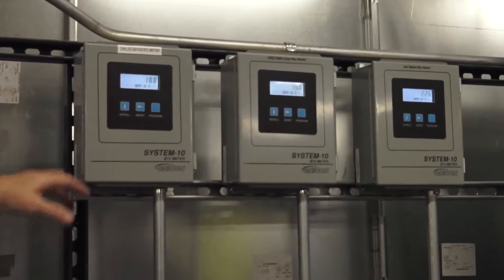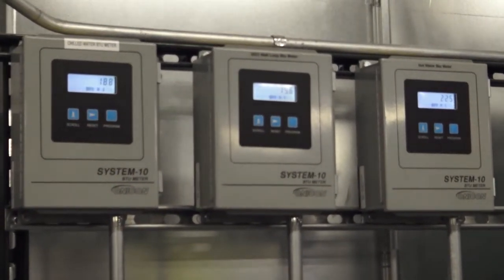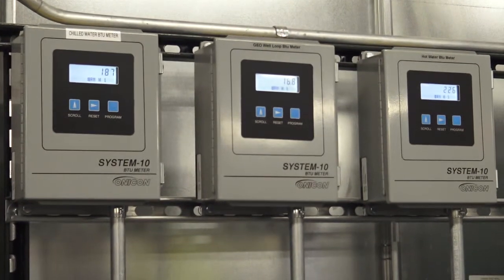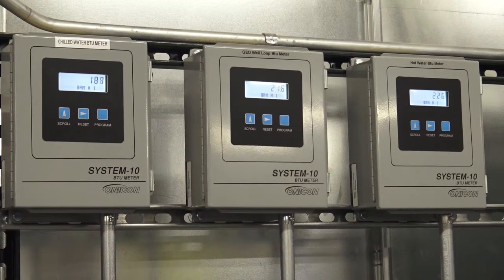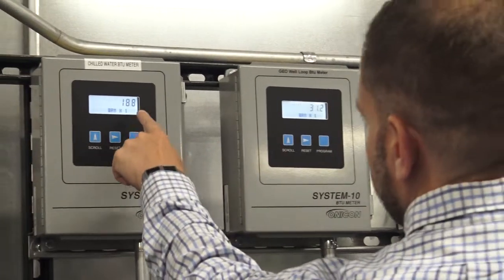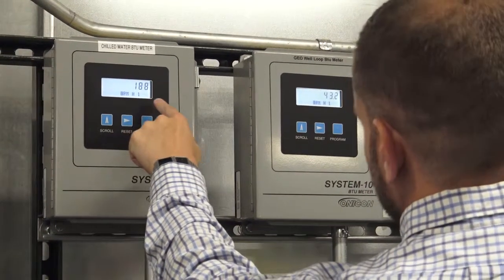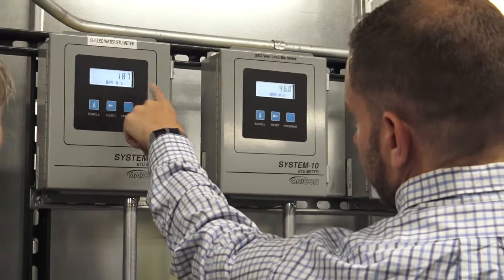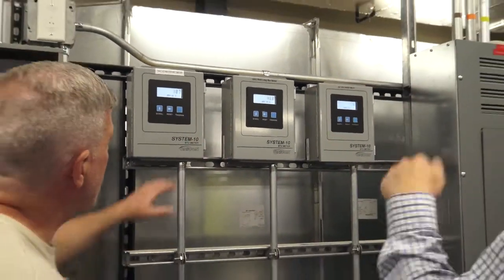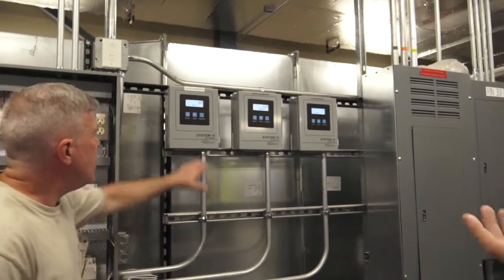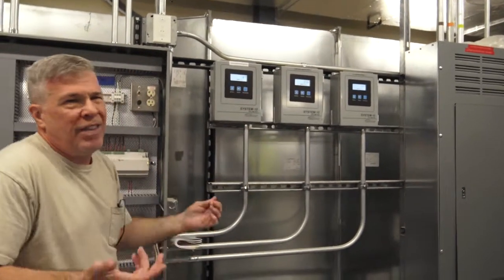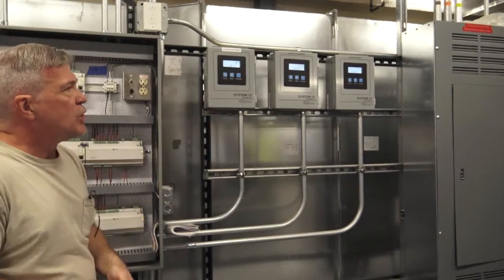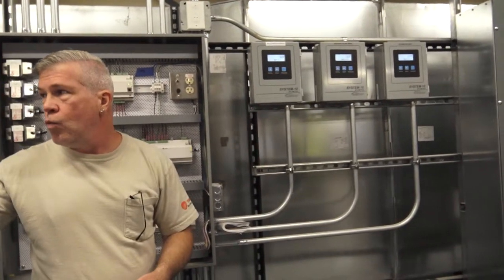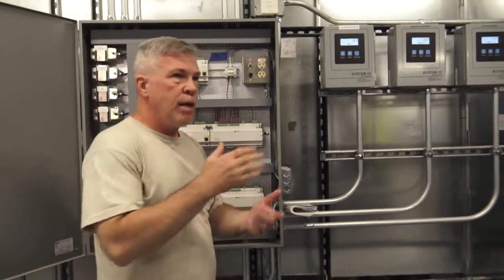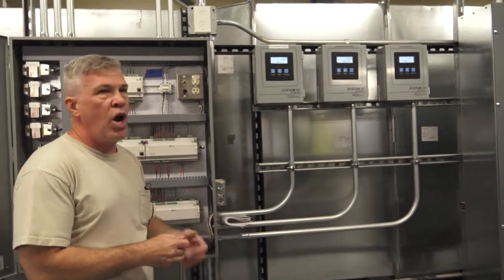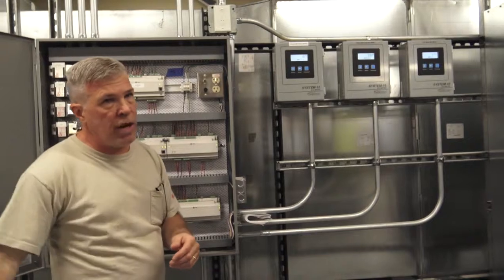It'll give you your flow rate, show you your temperatures on your supply returns, and then the BTUs that it's producing. So what is this, the flow rate? 188 gallons per minute. Should that be pretty constant, or does it vary? It will all just vary based on demand. The geo one usually fluctuates the most, because if the chiller is creating more hot water than it needs, or more chill water, then that flow will change based on what it's dumping out to the field.